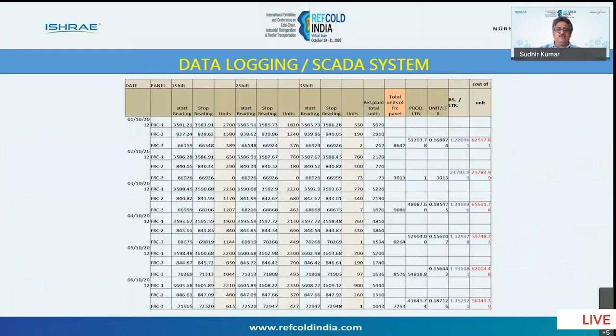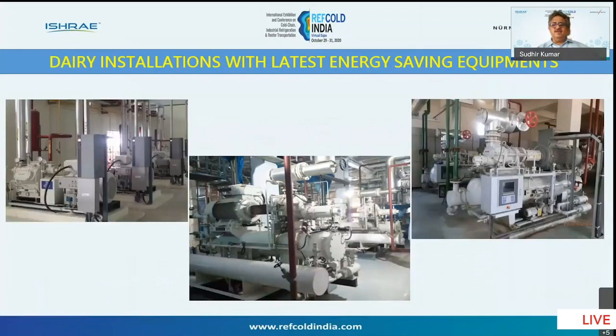You can have data logging so that you can also calculate trends. Basically, like last year, what was your power for this much liters of milk? Say, if you're having a 10 lakh liter dairy, it can calculate in a graphical form how much power you are consuming per liter of milk. And by doing that, you will also have a trend. So say you can see after 1 week for the same milk, if there is any increase in power, then you know there is something wrong in your plant and you can check the efficiency. So you can have a trend system, MIS system, so that you will have the complete data logged in, and you can even get it on your mobile phones. The owner can see how much was the power consumption today.